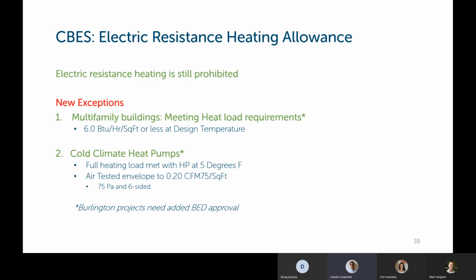So a new, pretty important addition to this 2020 code is that overall, same as the old code, electric resistance is prohibited from commercial buildings. So that's still the same, but there's a couple new exceptions in here. The first being multifamily buildings that are meeting pretty stringent heat load requirements can have electric resistance backup heating. And those are multifamily buildings with less than or equal to 6 BTU per hour per square foot heating load at design temperature. Those buildings could use electric resistance heating.